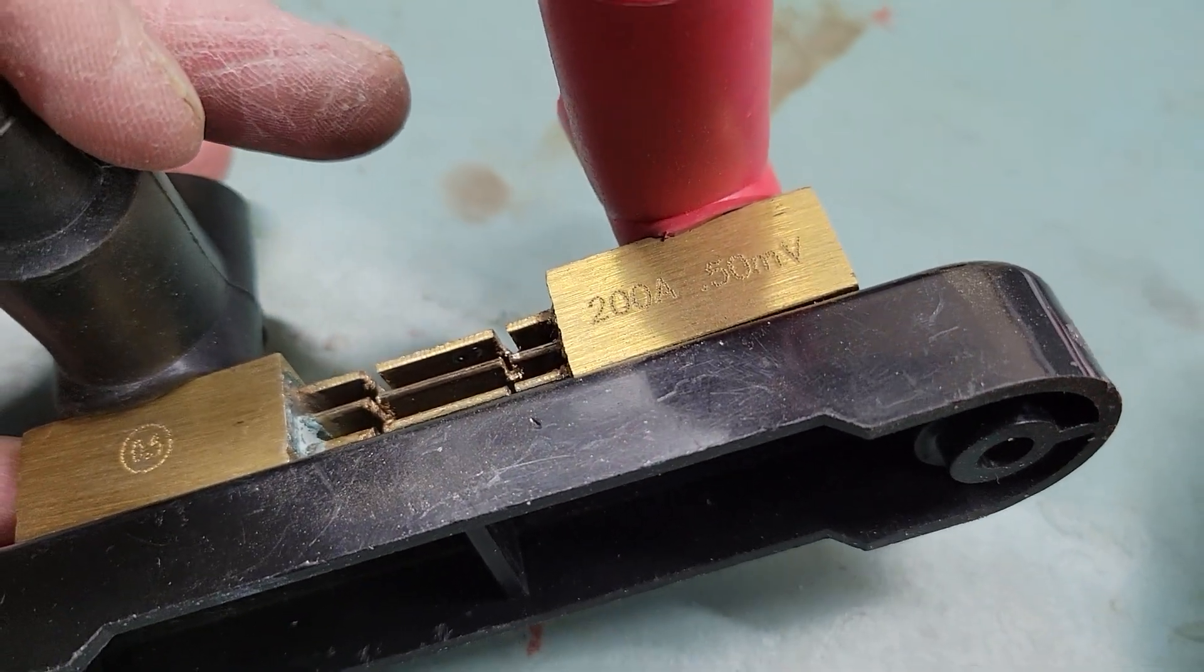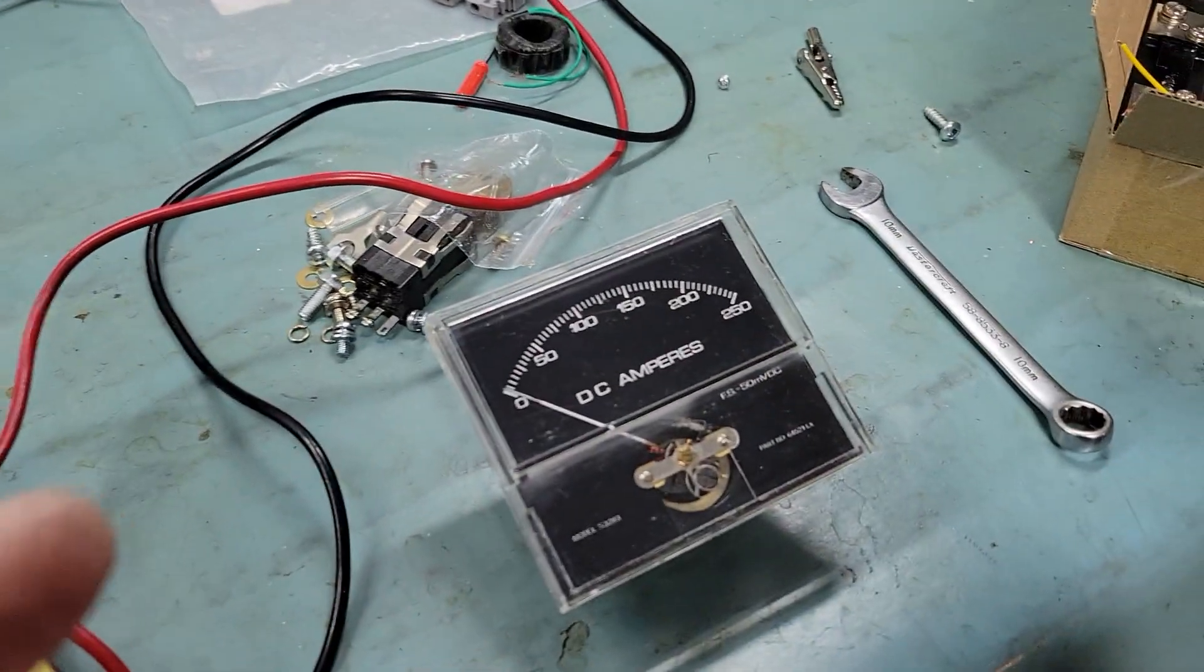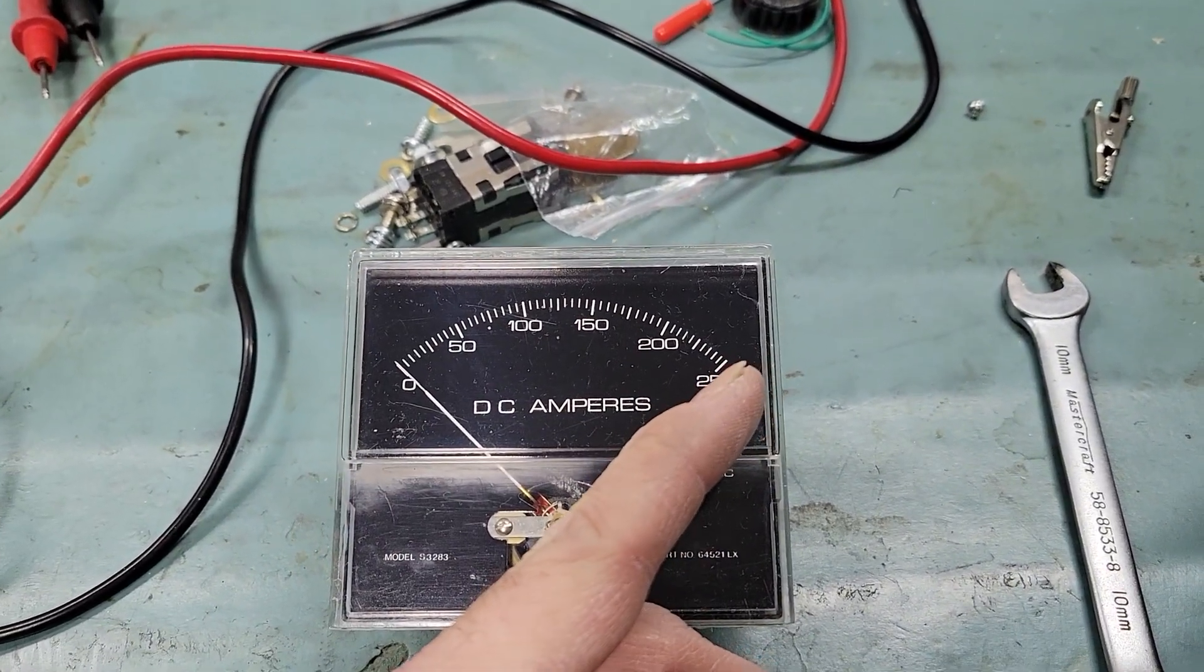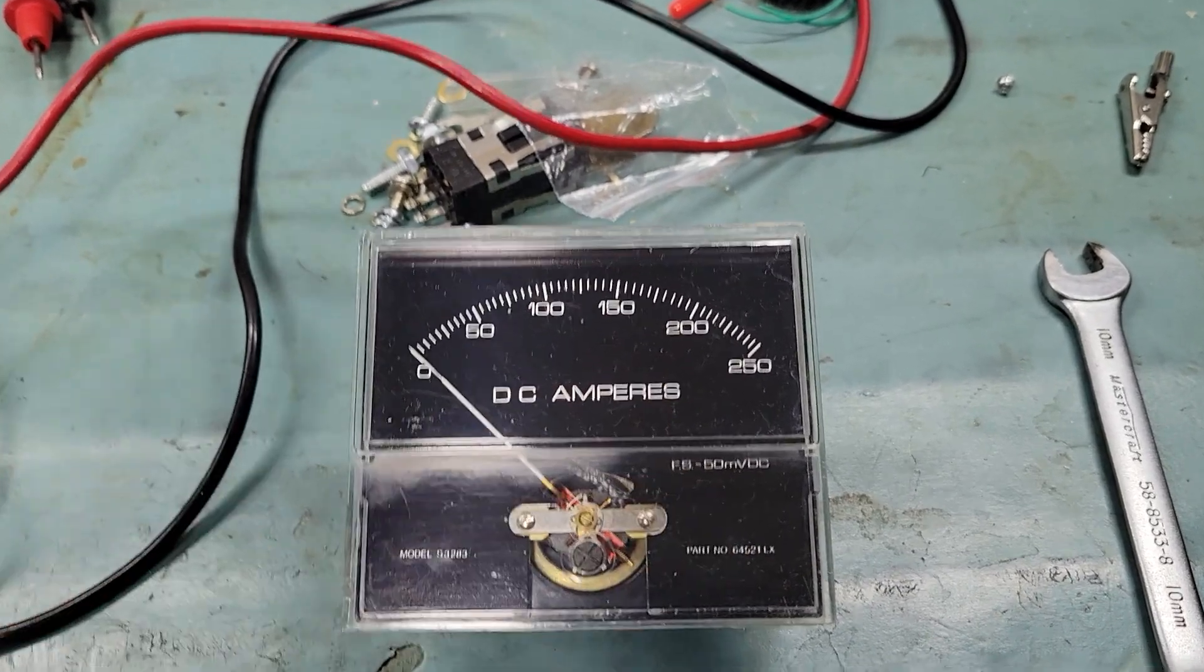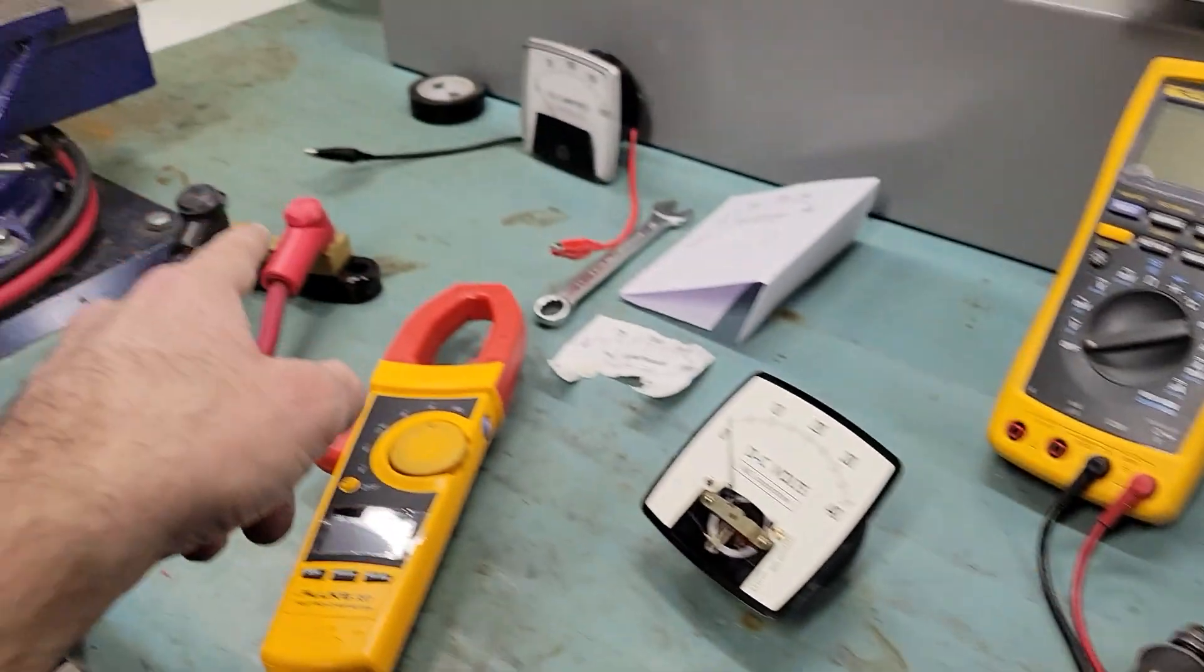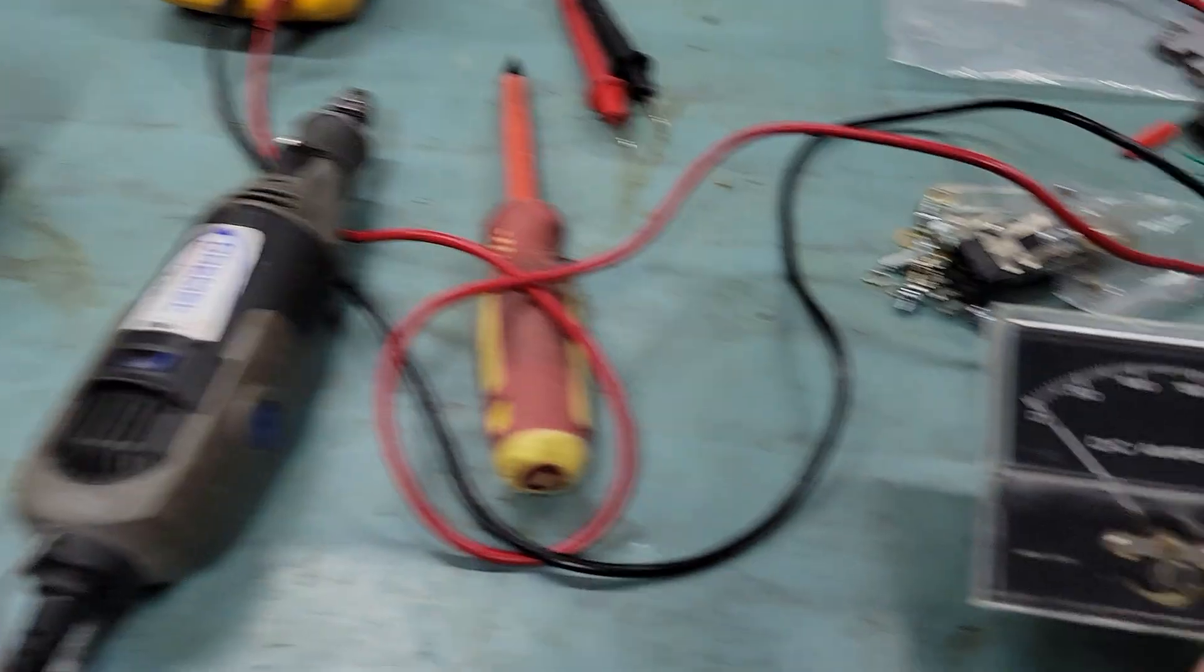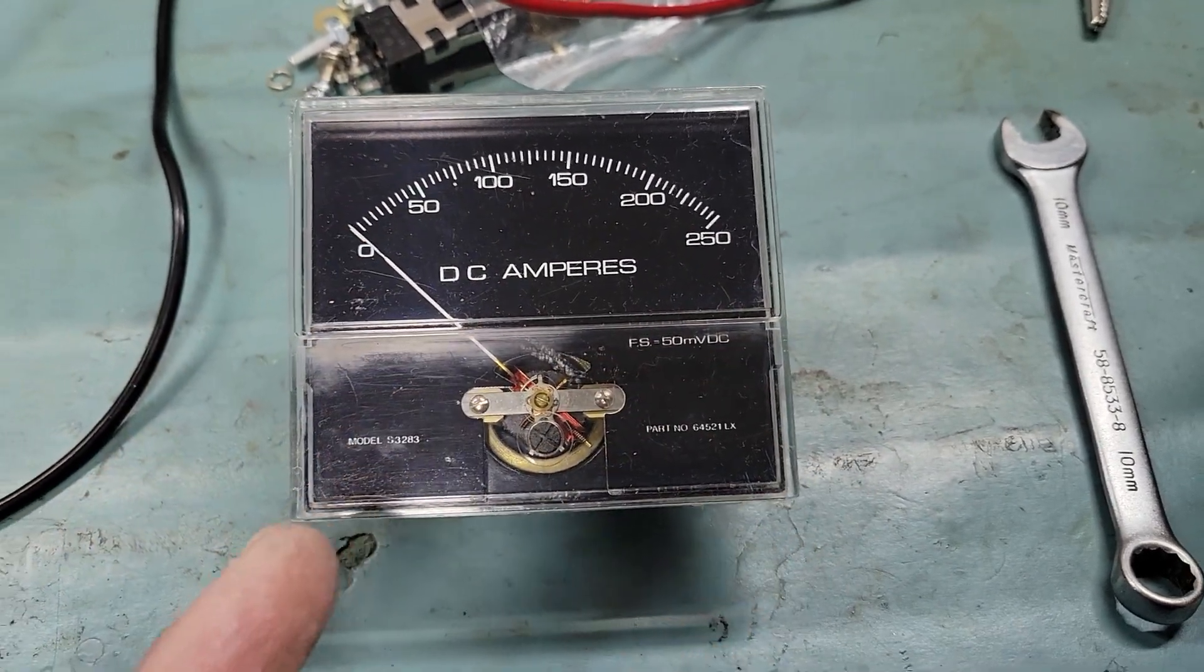This one here you see is a 200 amp 50 mV shunt. What I will need is a meter with 200 amps on the maximum reading and 50 mV. I could not use this one because if I apply 50 mV to this one, which corresponds to the 200 amps of this one, it will reach 250 amps, which does not correspond. So you need to tune it, and that is what I made.